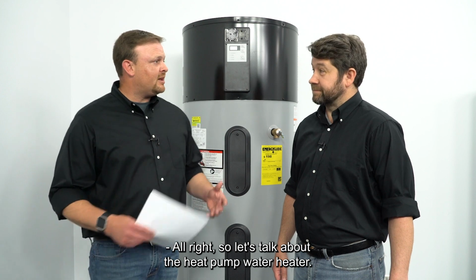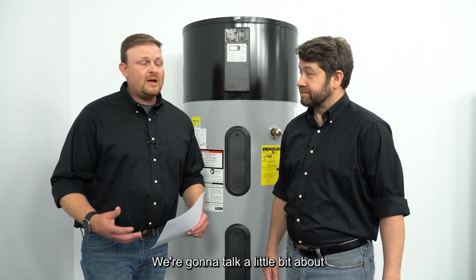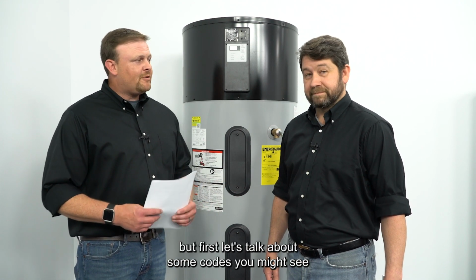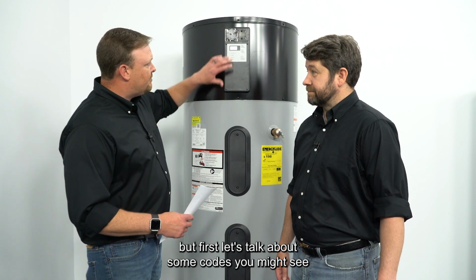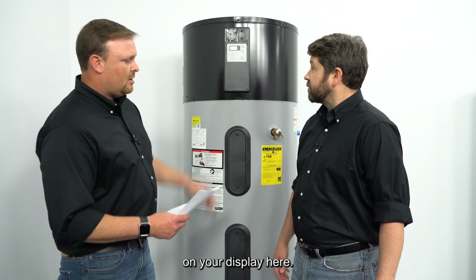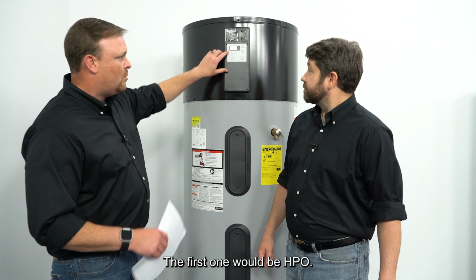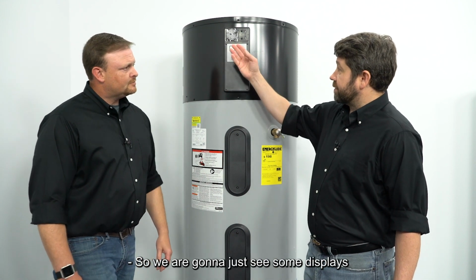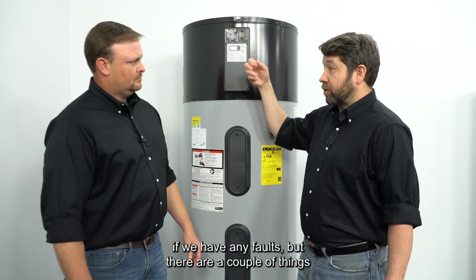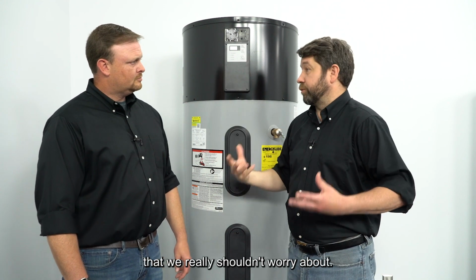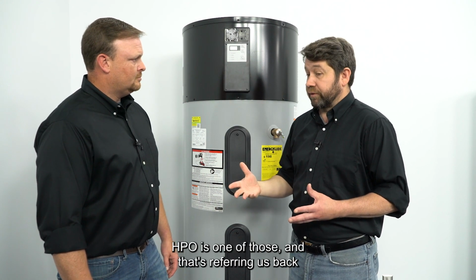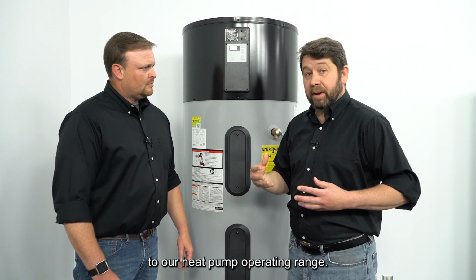All right, so let's talk about the heat pump water heater. We're going to talk a little bit about some of the top service items, but first let's talk about some codes you might see on your display here. The first one would be HPO. So we are going to see some displays if we have any faults, but there are a couple of things that are going to be displayed that we really shouldn't worry about. HPO is one of those, and that's referring us back to our heat pump operating range.